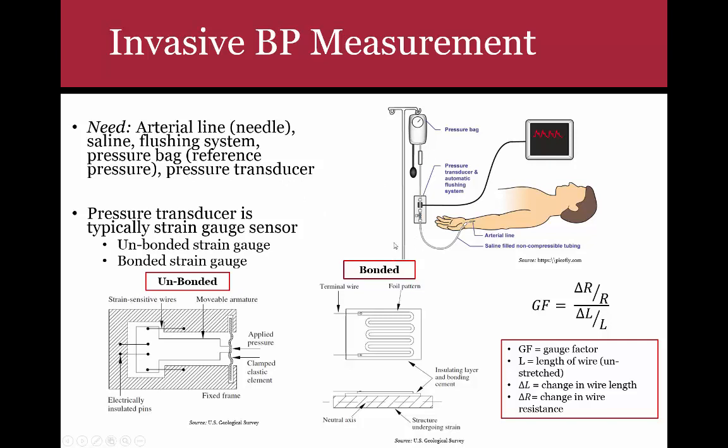And so the way it usually works is if you're at the bedside in a supine position, so like laying on your back, you have a tube connected to a pressure bag as your reference pressure, and the transducer will then flush out any blood, and then blood will interface here with saline. Saline and blood have around the same viscosity and density. So the pressure you measure down here will be measured up here.